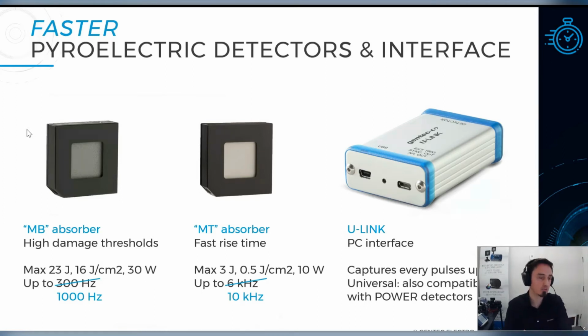First one with the MB absorber, which offers really high damage thresholds in terms of energy density, up to 16 joules per square centimeter, and now comes with up to 1 kilohertz capability. So 1000 hertz single pulse to pulse energy measurement capability. And with the MT absorber, the metallic one, which is faster by design, this one goes now up to 10 kilohertz. So good flexibility for measuring your laser pulse energies. And now with the new interface, the U-Link, to connect the probe to your computer, this one captures every pulse up to 10 kilohertz to provide, once again, a calibrated measurement.